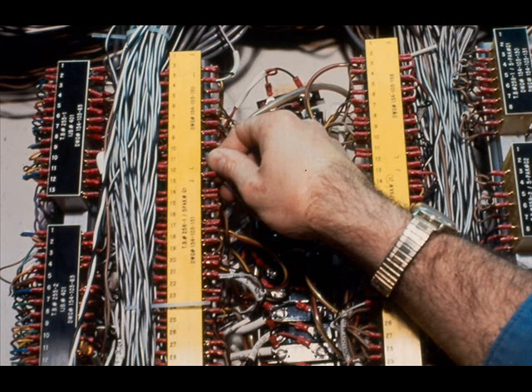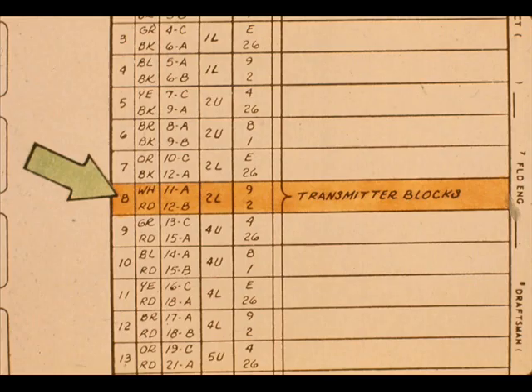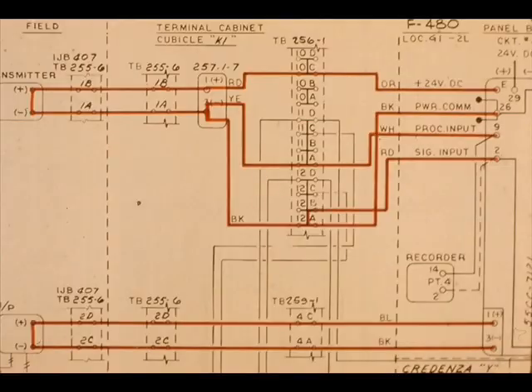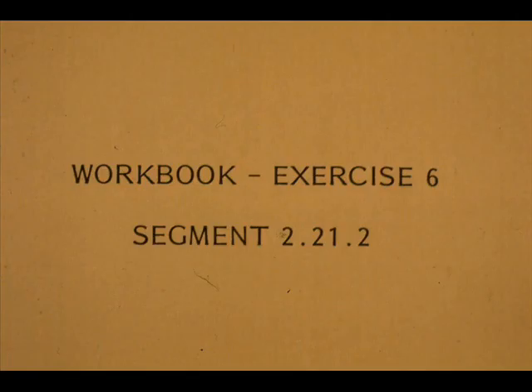Terminate the pairs on the transmitter terminal block as per the loop diagram, or the cable termination schedule. Color the wiring that is complete. Now work exercise number 6 in your workbook.